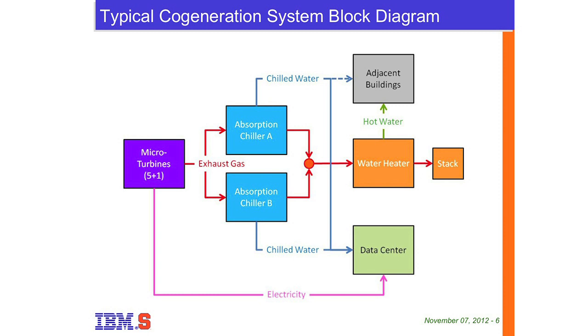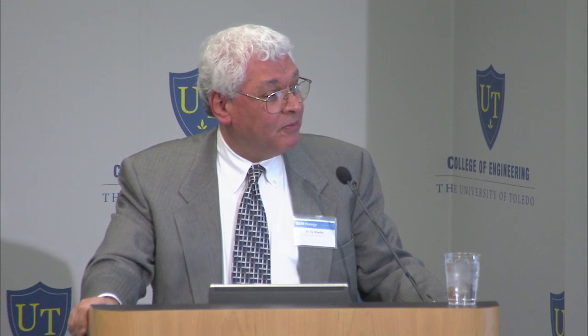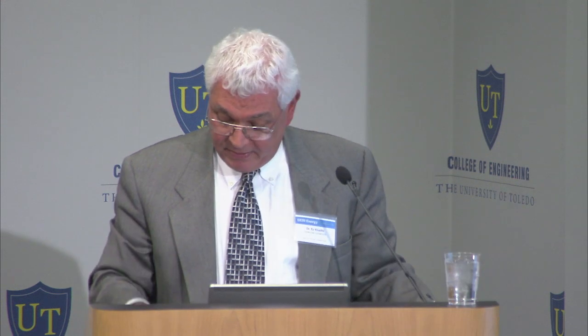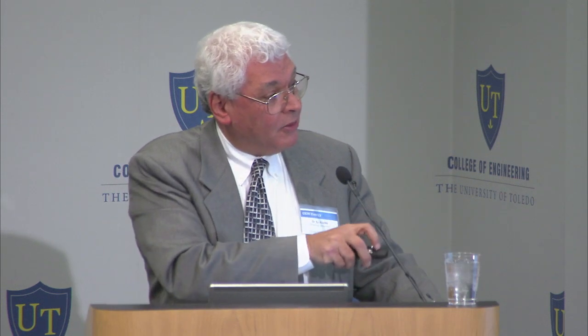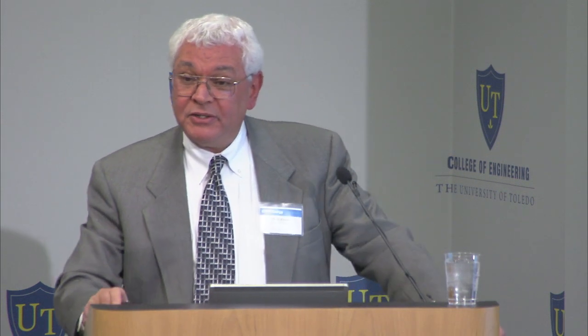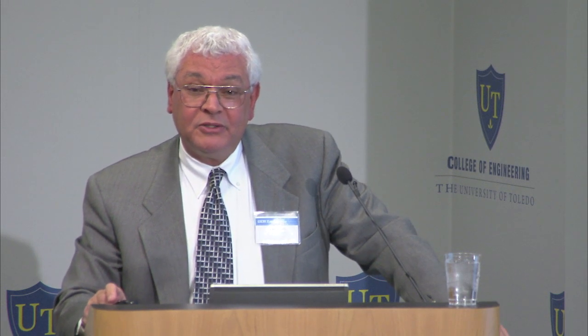You take the electricity from the turbine and it goes to feed the data center. Then you take the waste heat into a cooling system called an absorption chiller. It's a thermochemical device that runs on heat and generates cooling. Then that cooling, some of it may go to the data center, as you see at the bottom there. So some of it provides the cooling for the data center for free in this case.